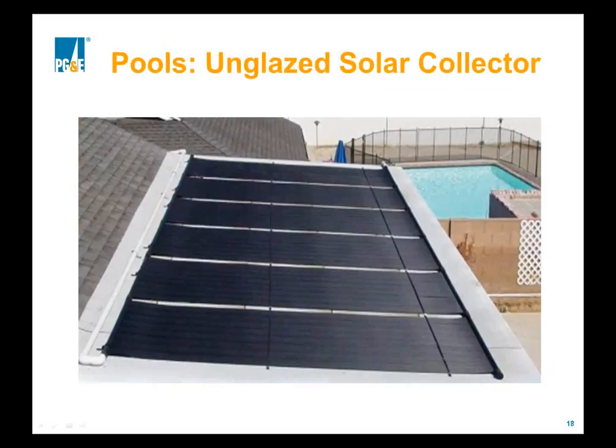So of OG300 certified collectors, there are a number of different technologies out there. Most commonly seen in California, I think, is the solar pool heating market, which has continued to be fairly active for the last 30 years or so. These are typically plastic or polymer type collectors. They're fairly low cost, and fairly efficient at heating water to low temperatures, but not the most efficient at heating water to higher temperatures. Next slide.